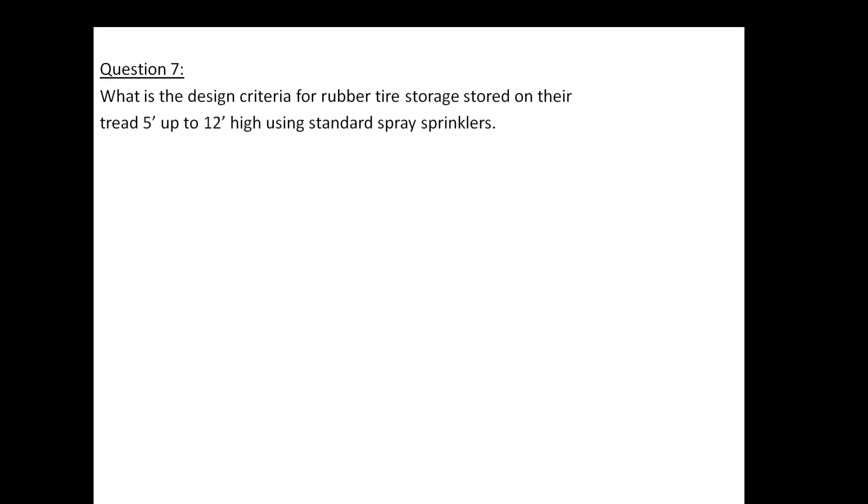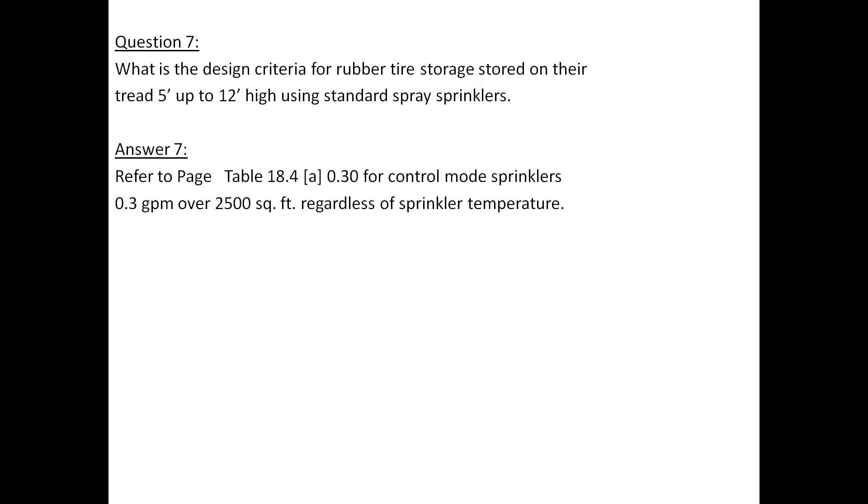Question 7: What is the design criteria for rubber tire storage stored on their tread 5 up to 12 feet high using standard spray sprinklers? The answer to question number 7: Refer to table 18.4A. 0.3 for control mode sprinklers. 0.3 GPM over 2500 square feet regardless of the sprinkler temperature.